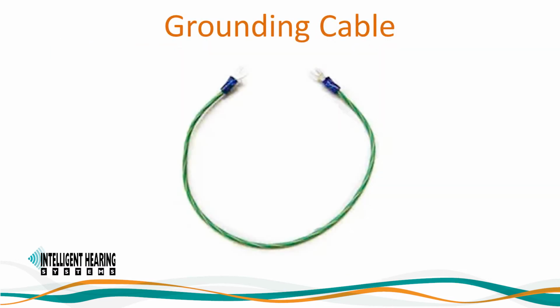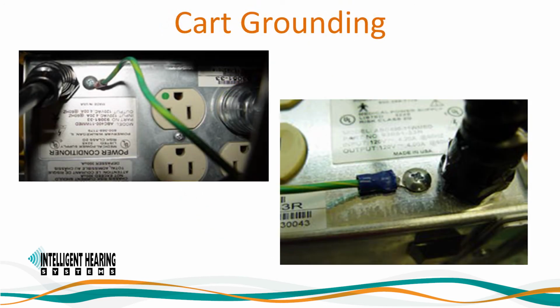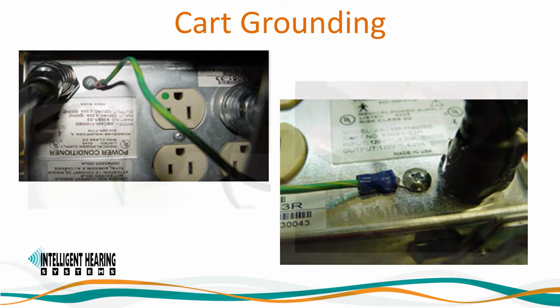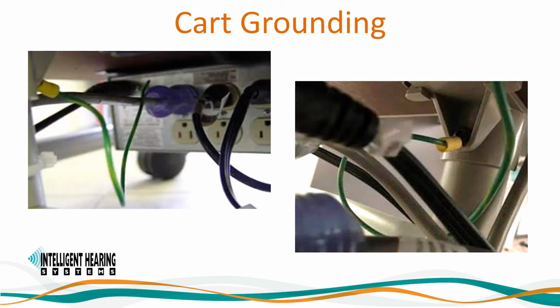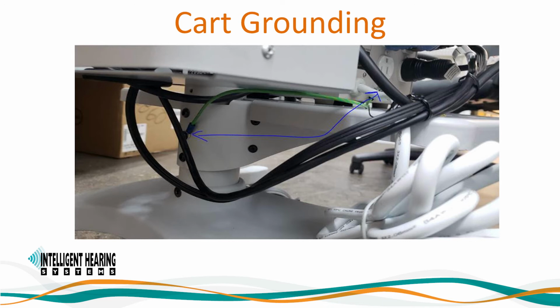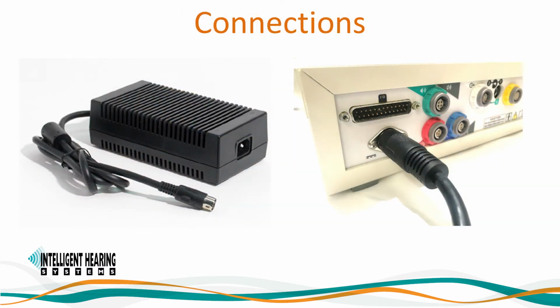This is done by connecting a grounding cable as shown here from the isolation transformer to the post of the metal cart. Connect the U metal piece under the screw of the isolation transformer and tighten. Then connect the other U under the screw that is located on the post of the metal cart and tighten. Here is another example of the grounding connection on the current IHS mobile cart. Secure connections for all power supplies are important. If the device has an external power supply like the Universal Smart Box, then secure the power supply to ensure that the cable is not loose or slipping out where it connects to the device.